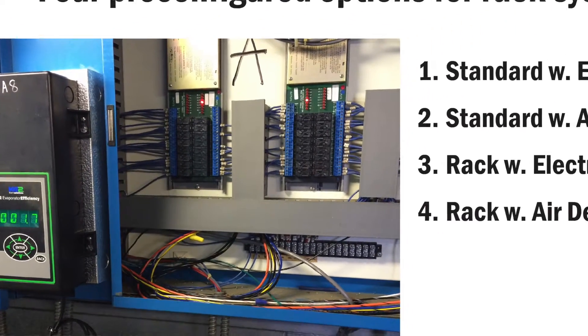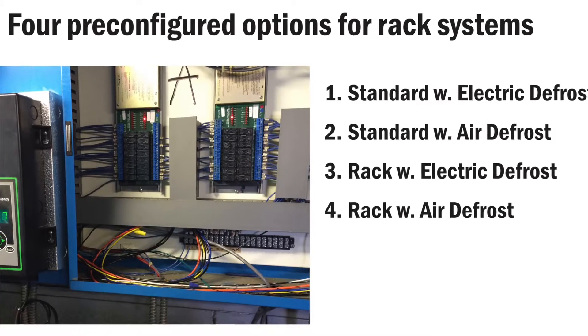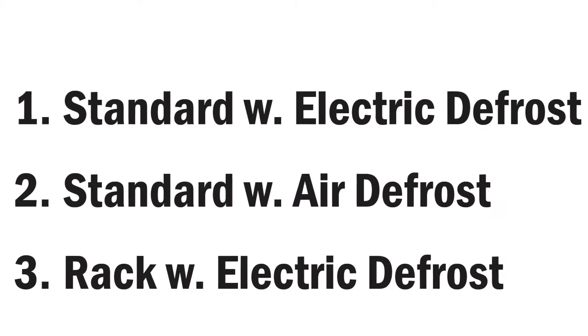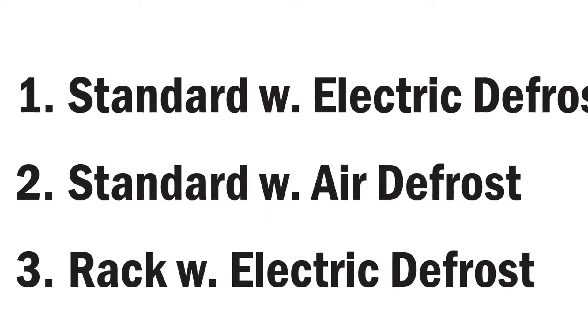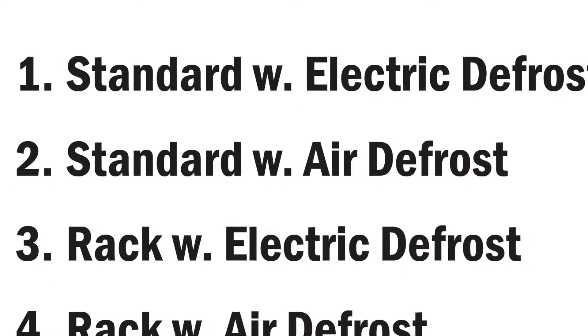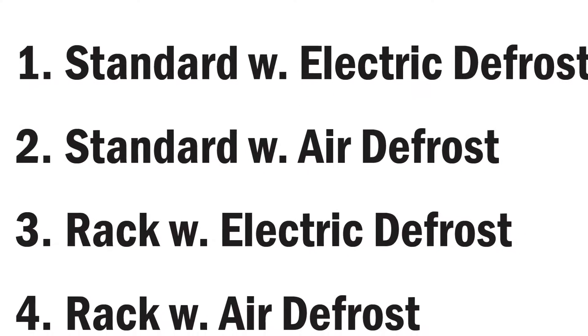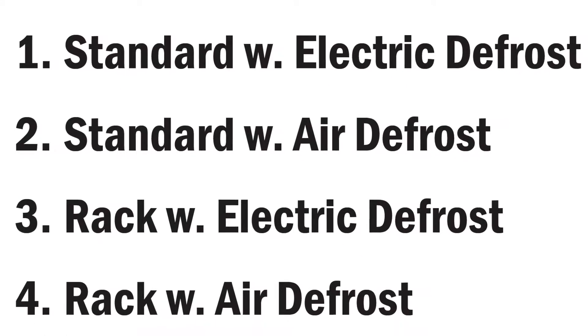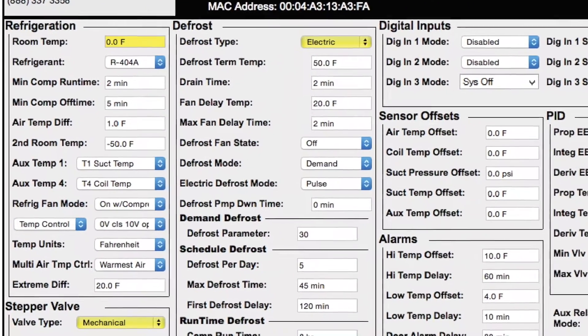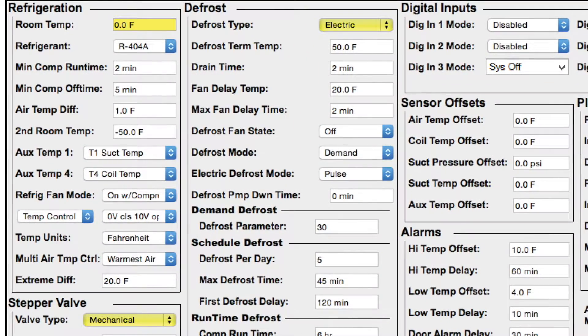Then we developed features for the KE2 Evap RE that were specifically tailored for managing the unique challenges associated with rack systems. The KE2 Evap RE has four pre-programmed options. It still offers standard control with electric defrost and standard control with air defrost, but now it adds the ability to configure rack control with electric defrost and rack control with air defrost.